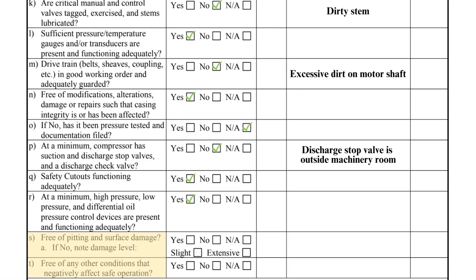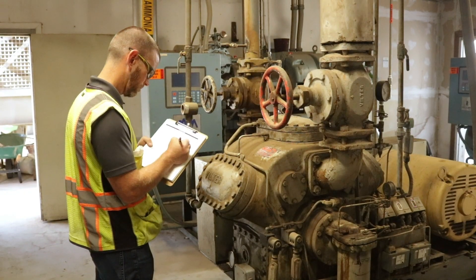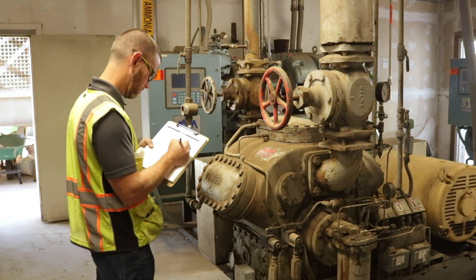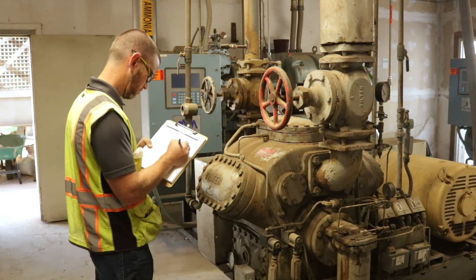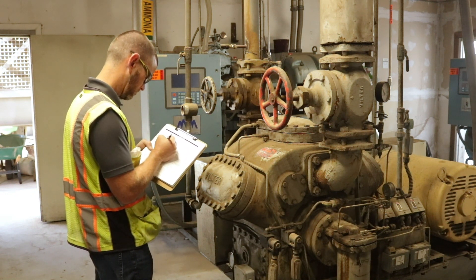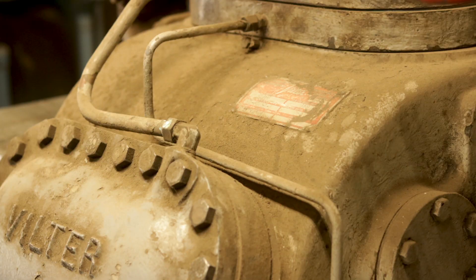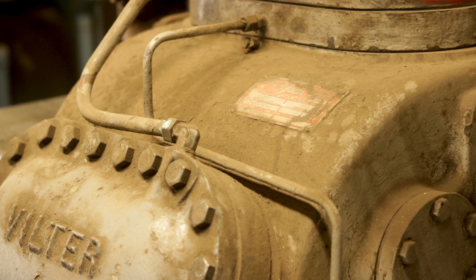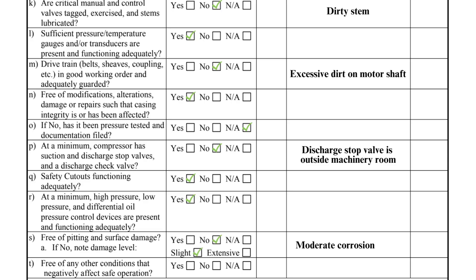The second page of the inspection checklist concludes with items S and T. Item S requires the entire surface of the compressor to be inspected, and any surface corrosion or pitting must be recorded as a deficiency. If a deficiency is noted, an additional checkmark is required for whether there is slight pitting or damage or extensive pitting or damage. This reciprocating compressor has moderate corrosion and dirt on the exterior that requires corrective measures.